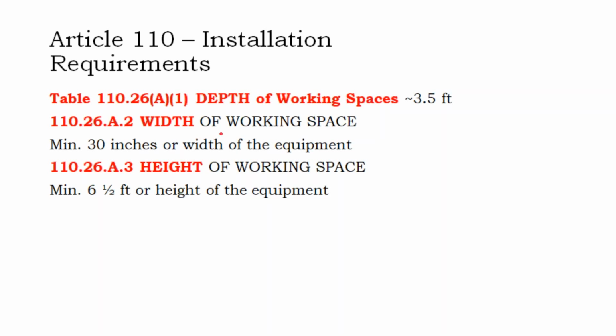And that is not an accessible location—you don't have your 3.5 feet of working space because you're up against the wall. So that's a code violation, just taking your batteries and putting the long end of them against the wall. I'm not sure an inspector would know enough to fail you on that, but in your most aggressive jurisdictions, you could fail inspection for that reason.